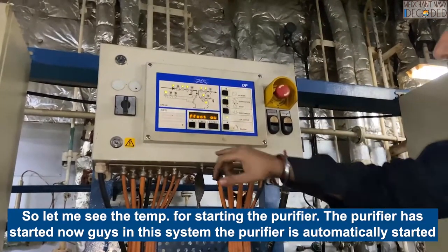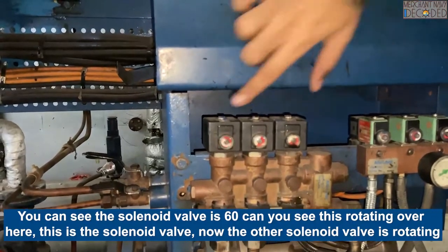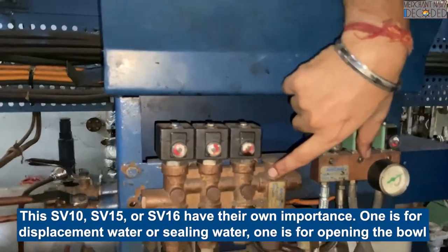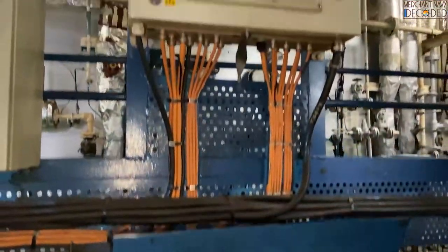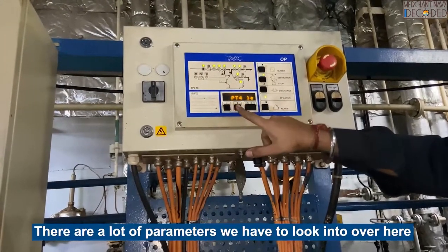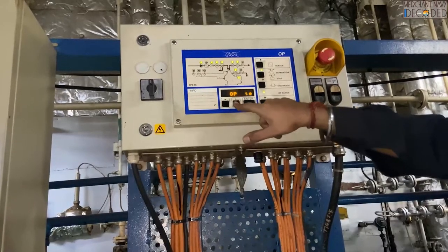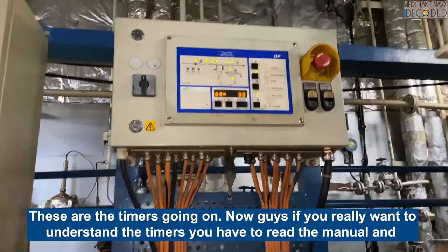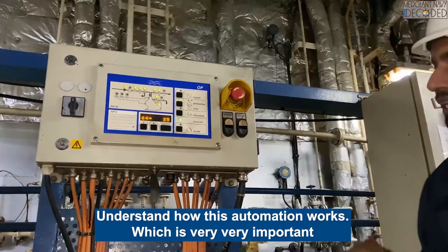In this system the purifier has automatically started. You can see the solenoid valve SB16 rotating over here - this is the solenoid valve. The other solenoid valve is rotating. SB10, SB15, SB16 have got their own importance: one is for displacement water or sealing water, one is for opening the bowl, one is for closing the bowl. There are a lot of parameters to look into. These are the timers going on - if you really want to understand the timers, you have to read the manual and understand how this automation works, which is very very important.